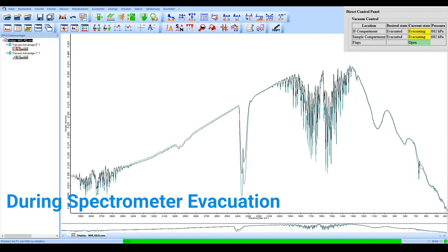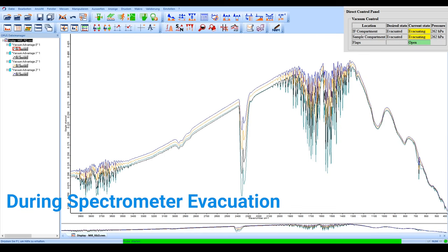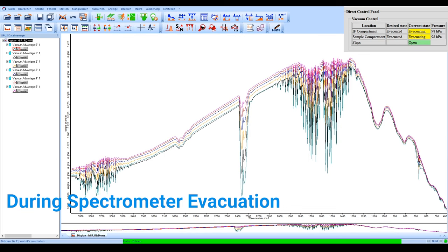Hello, I'm here today to talk to you about the advantages of vacuum conditions in FTIR spectroscopy. These advantages become obvious when you're looking at the single channel spectra upon evacuation of the system. Over time, with decreasing pressure, you can clearly see how the signal is increasing. At the same time, the disturbances coming from water and CO2 are drastically reduced. This gives you an overall better signal-to-noise ratio and very stable background conditions.